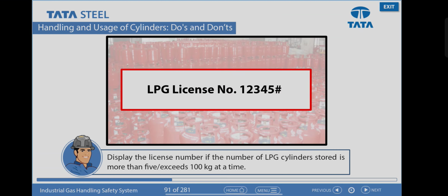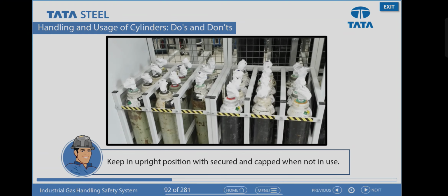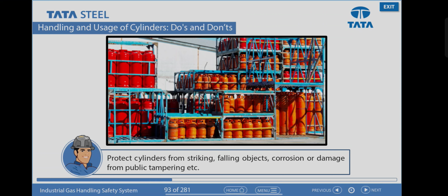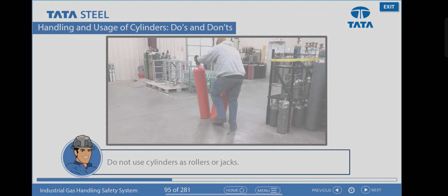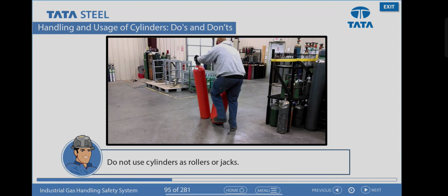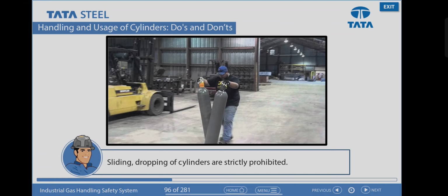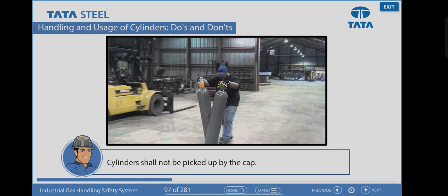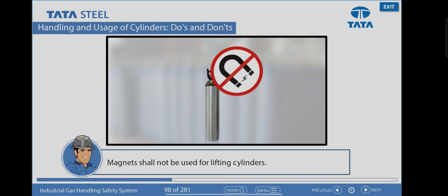Display the license number if the number of LPG cylinders stored is more than 5 or exceeds 100 kilograms at a time. Keep in upright position, secured and capped when not in use. Protect cylinders from striking, falling objects, corrosion or damage from public tampering, etc. Damaged or leaking cylinders must be reported immediately for proper disposal. Do not use cylinders as rollers or jacks. Sliding and dropping of cylinders are strictly prohibited. Cylinders shall not be picked up by the cap. Magnets shall not be used for lifting cylinders.